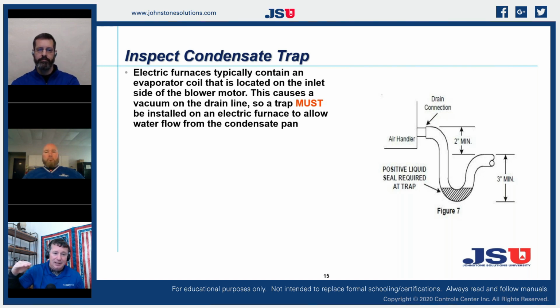If that is an inline style trap, there's not enough room there. That trap is just a little bucket, maybe an inch deep, to hold water in. It's only able to be used on the positive pressure side of a system. So on that negative side, we have to have that clearance so that when we have a restriction on our return side, when our blower is pulling hard, trying to keep its airflow moving, our water is actually inclining up that stand, that minimum 2-inch stand. And if we have very high static, we're going to pull all that water right back into our unit.